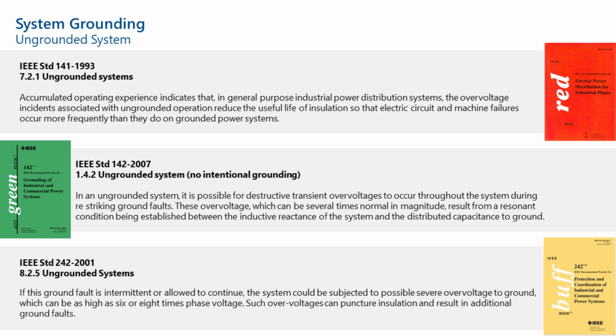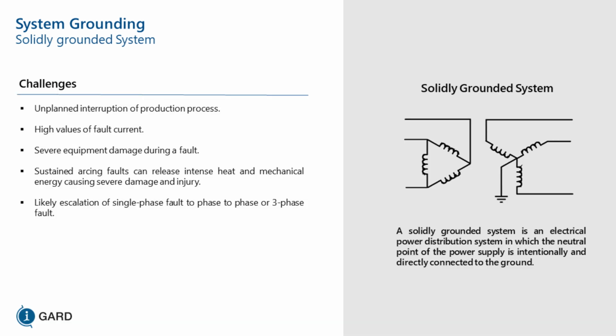So in ungrounded systems, from the Green Book, you have destructive transient overvoltages. You have to keep in mind you can get up to 6 to 8 times transient overvoltages with respect to arcing ground in an ungrounded system. Arcing ground faults are likely going to occur in a motor someplace. And the Buff Book, is that the Buff Book? It says the same thing.